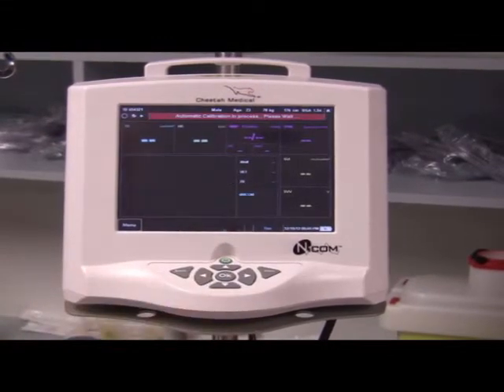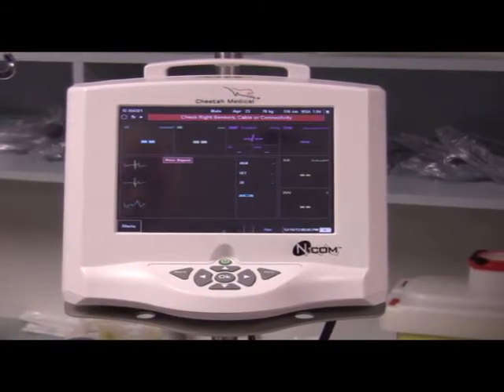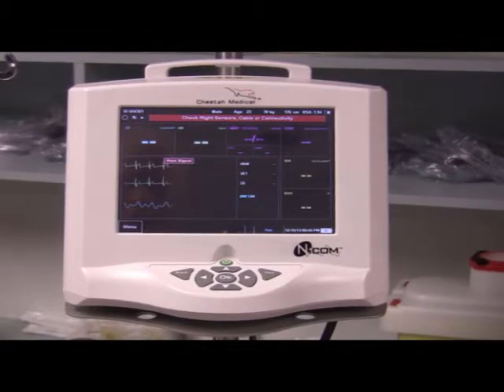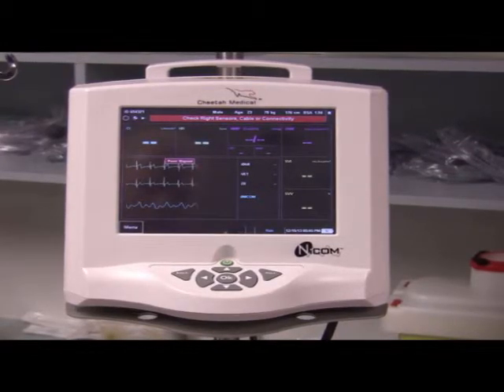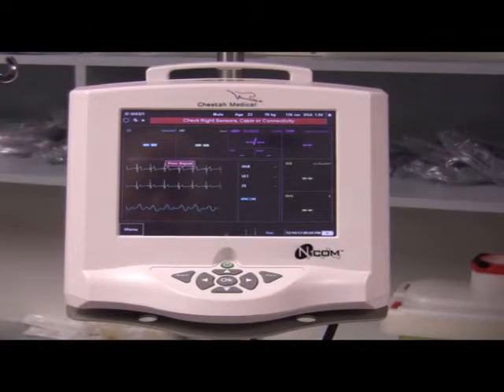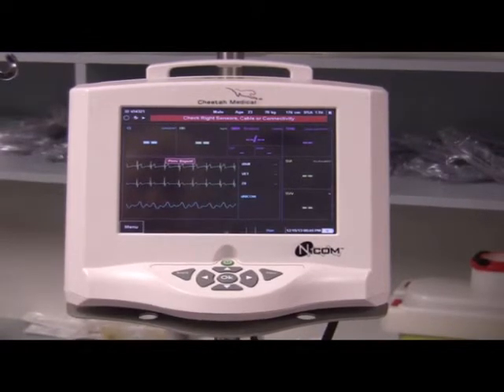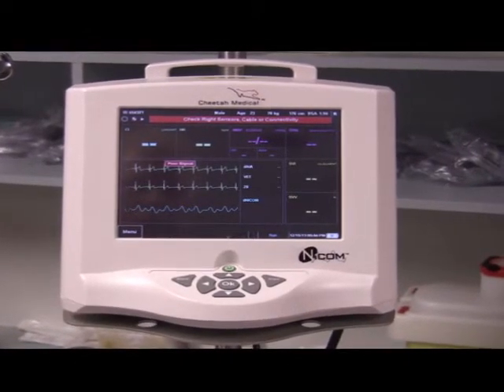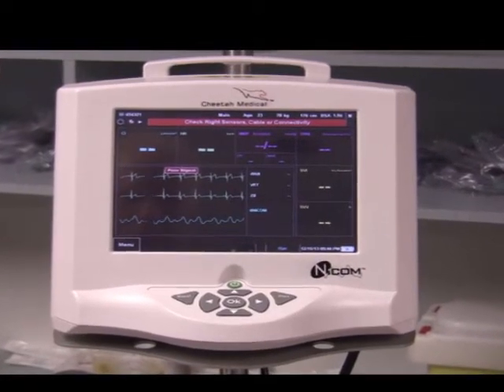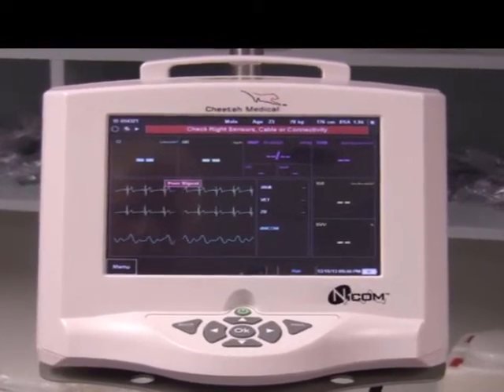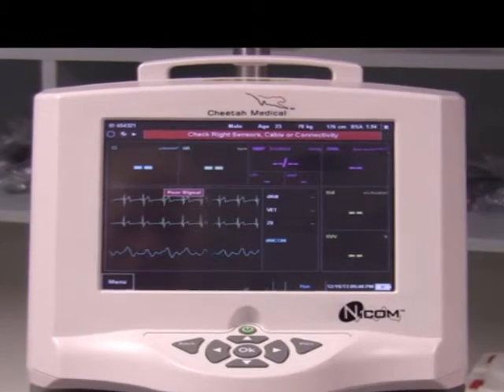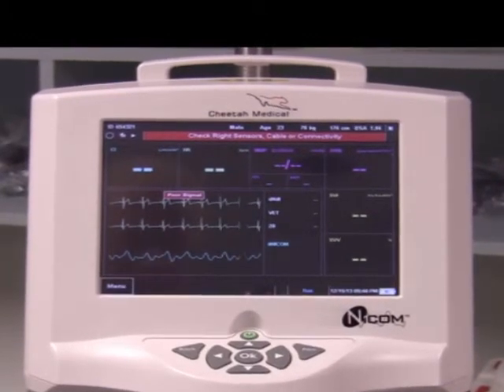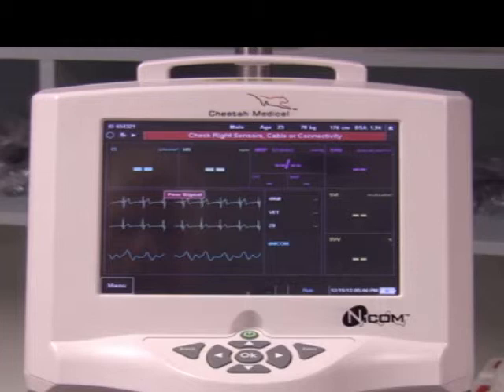When the NICOM sensors are applied and connected to the monitor, a self-diagnostic calibration test is performed, and the quality of the signal is evaluated. The time required to perform the calibration is typically 90 to 120 seconds. To minimize the calibration time, the patient should be instructed to refrain from moving or speaking. Occasionally the signal may be inadequate, and an error message will appear which identifies which sensor is faulty and needs to be checked or changed.